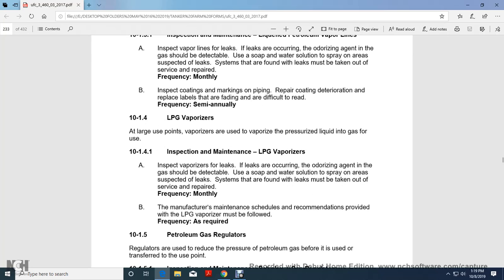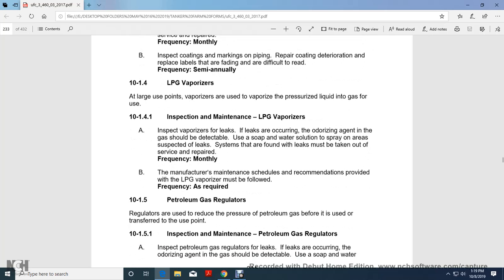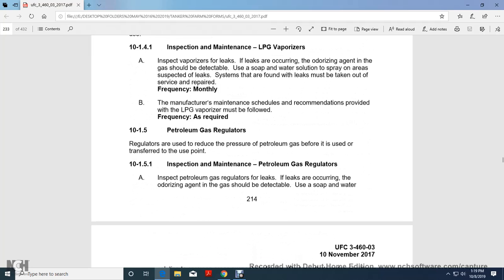Liquid Petroleum Gas Vaporizers. Vaporizers are used to vaporize pressurized liquid petroleum gas for use. Inspection and maintenance of liquid petroleum gas vaporizers: inspect vaporizers for leaks—if leaks are occurring, the odorizing agent in the gas should be detectable. Use soap and water solution and spray suspected leak areas. Leaks must be taken out of service and repaired. Manufacturer maintenance schedules and recommendations for the liquid petroleum gas vaporizer must be followed at the required frequency.